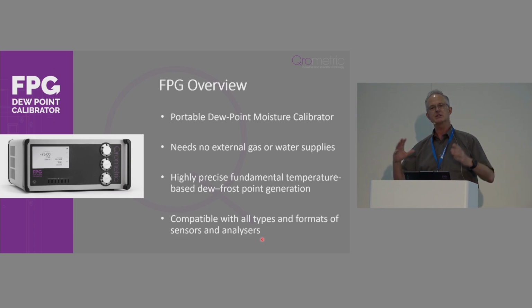You need no external gas supplies or water supplies. It's self-contained and very easily adaptable for use on site. And it's a very precise system. It's based around the same principles as the 2 pressure generators, using temperature and pressure. So it's fundamental, SI traceable, high-level performance. And because of our experience in the field, we've made it so it's compatible with any type of moisture analyzers. So dew point sensors, P2O5 analyzers, all the different types of units that are out there.